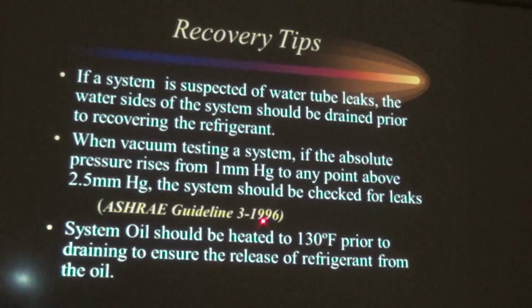ASHRAE Guideline 3-1996. This one I want to point out. The test question doesn't ask this. It says pressure rises from 1 millimeter to 1.5. They make you add this number, add 1.5 to 1 to get this number. So just be aware of that. System oil should be heated to 130 degrees prior to draining to ensure the release of refrigerant from the oil.